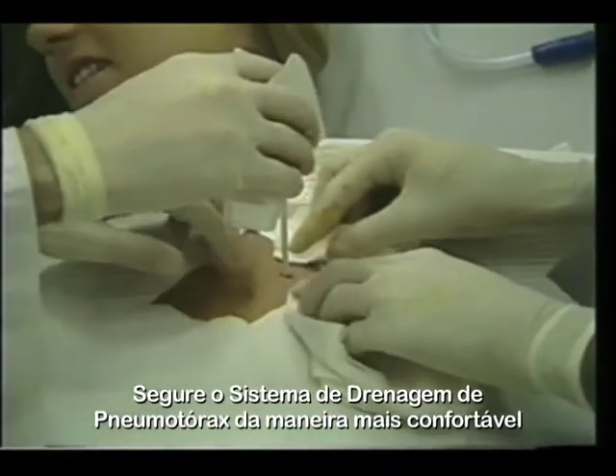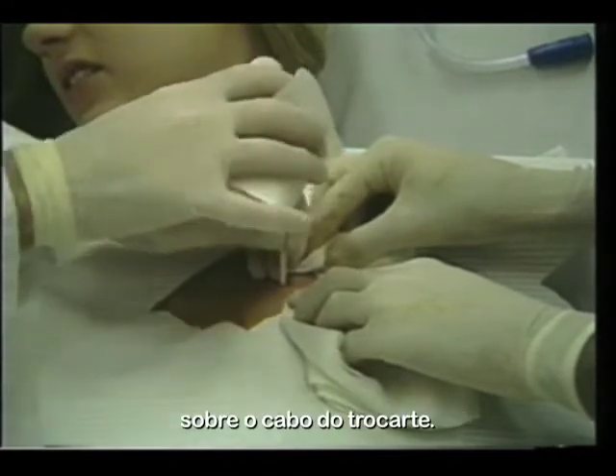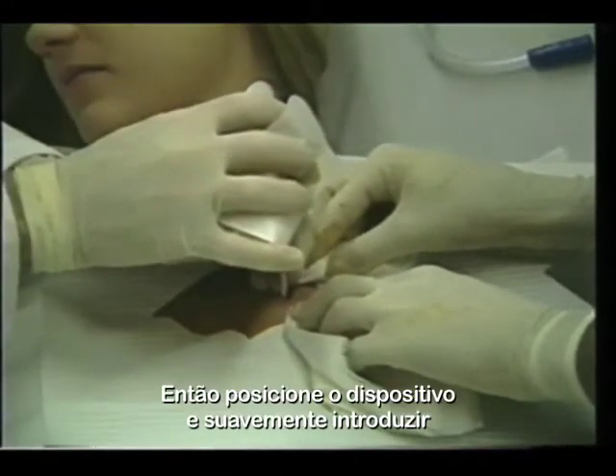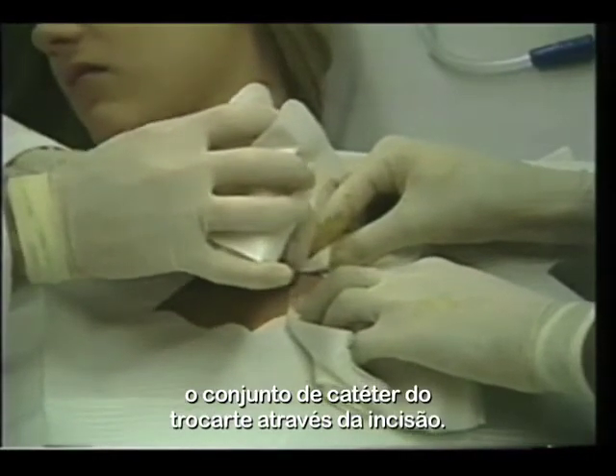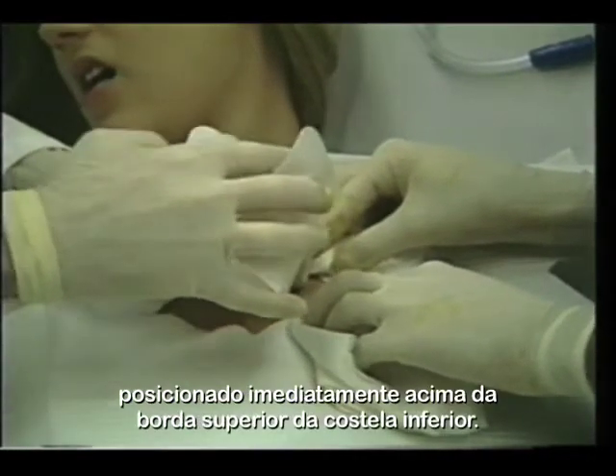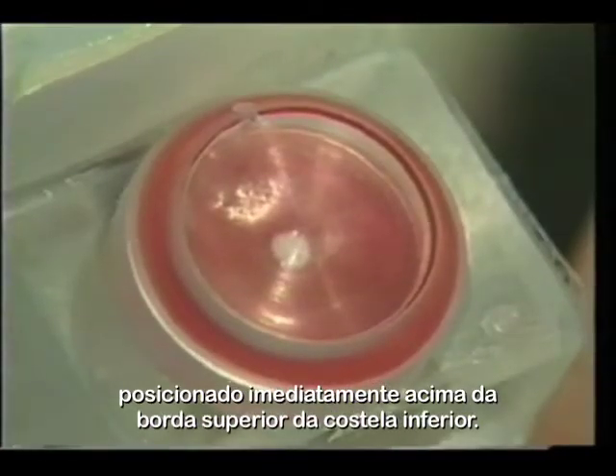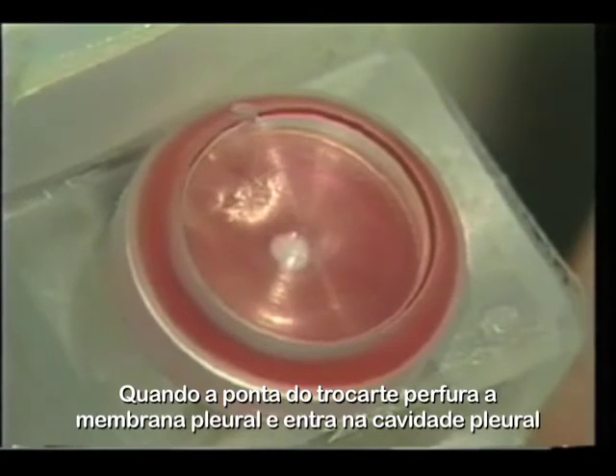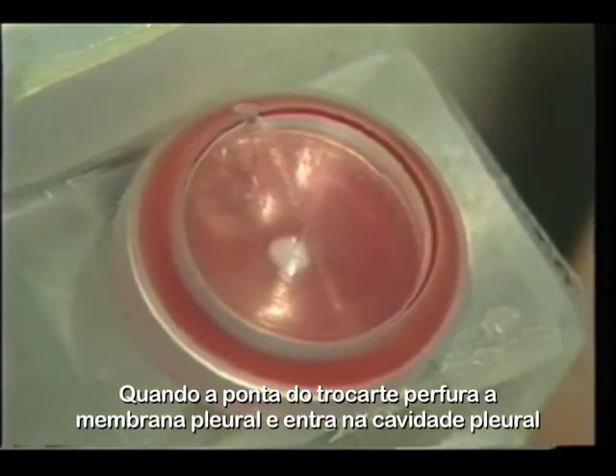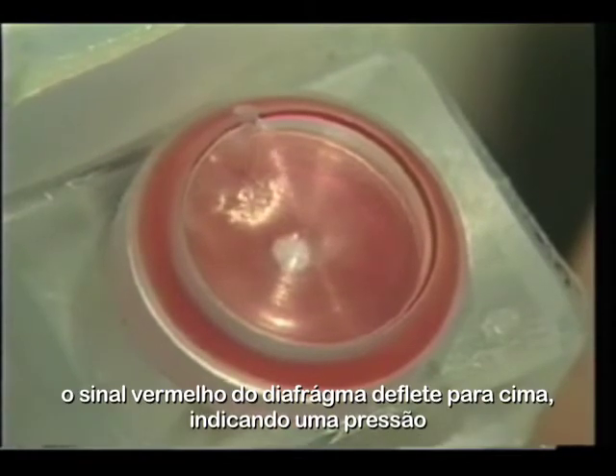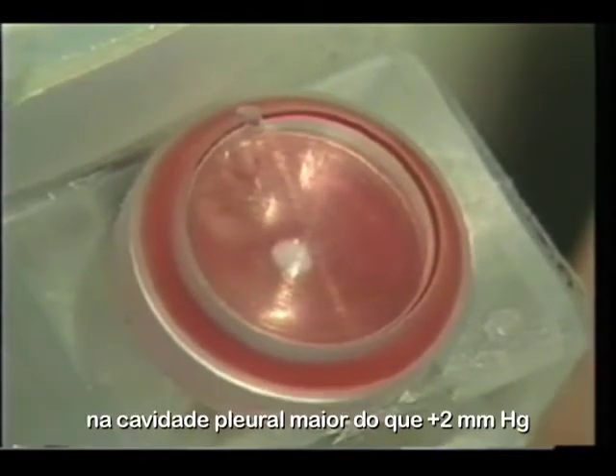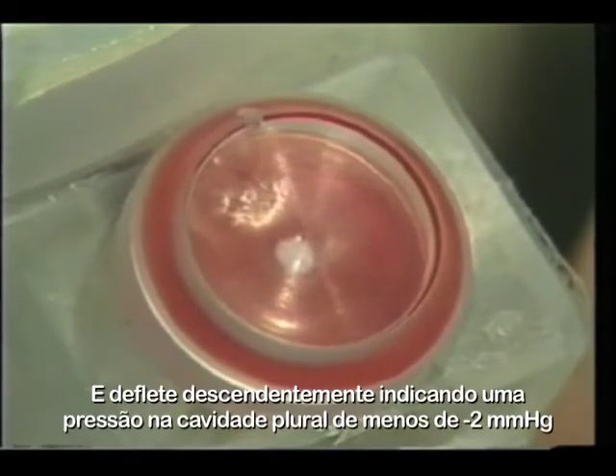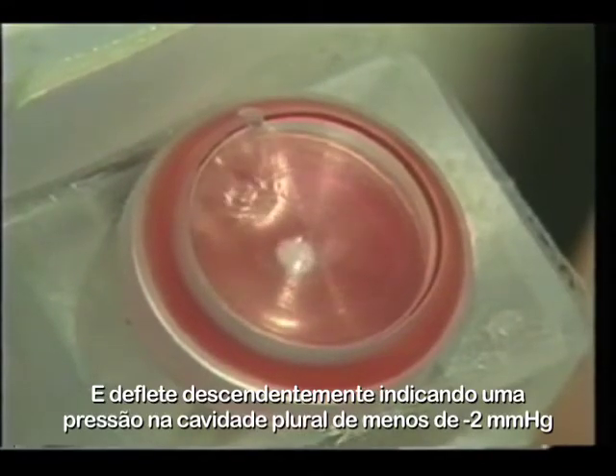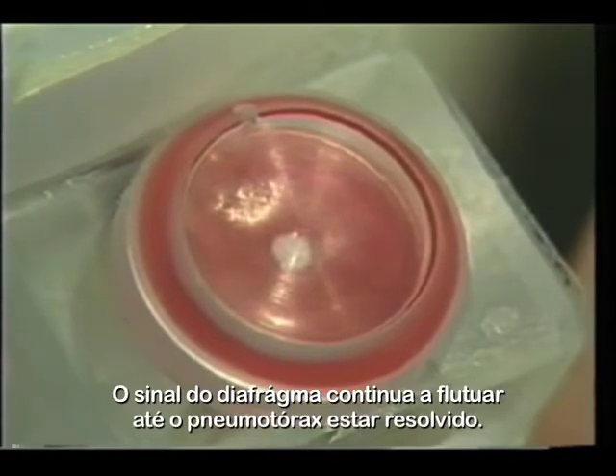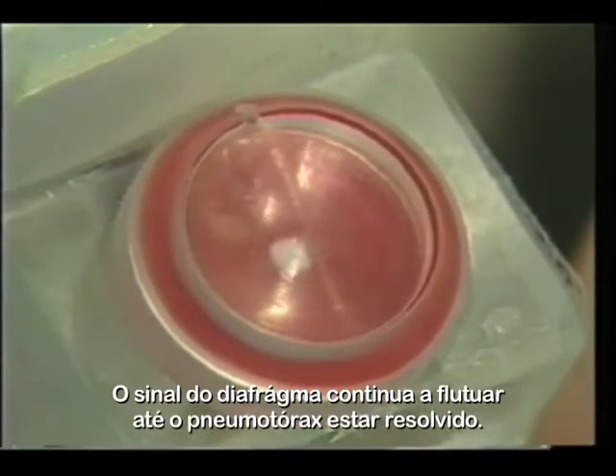Grasp the thoracic vent in the most comfortable manner with the thumb or first digit over the trocar handle. Then position the device and gently introduce the trocar catheter assembly through the incision, staying immediately above the superior border of the lower rib. When the trocar tip perforates the pleural membrane and enters the pleural cavity, the red signal diaphragm deflects upward, indicating a pressure in the pleural cavity greater than +2 millimeters of mercury, and deflects downward, indicating a pleural cavity pressure of less than -2 millimeters of mercury. The signal diaphragm continues to fluctuate until the pneumothorax is resolved.